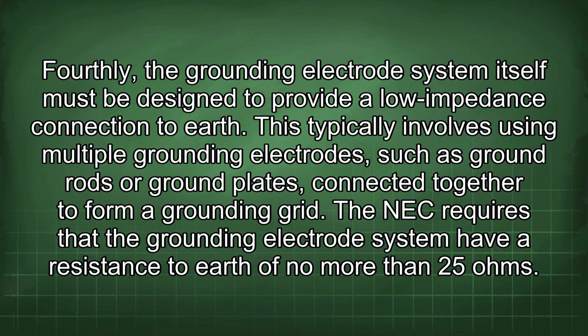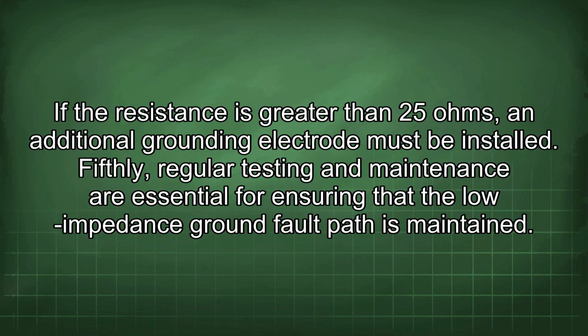The NEC requires that the grounding electrode system have a resistance to earth of no more than 25 ohms. If the resistance is greater than 25 ohms, an additional grounding electrode must be installed. Fifthly, regular testing and maintenance are essential for ensuring that the low impedance ground fault path is maintained.